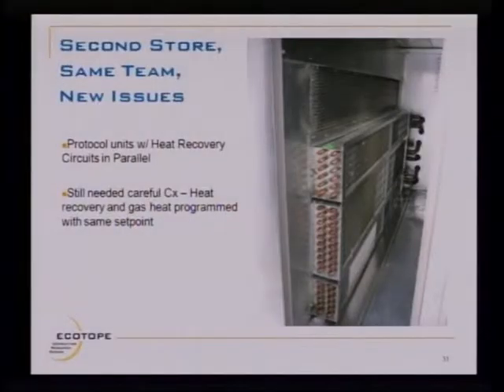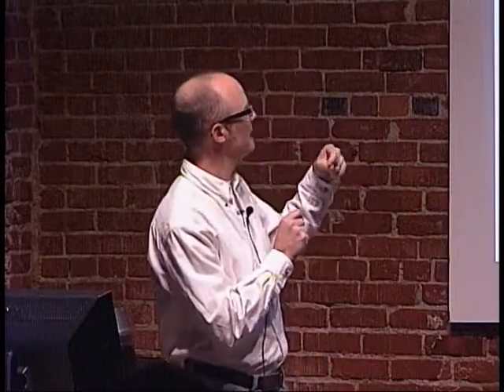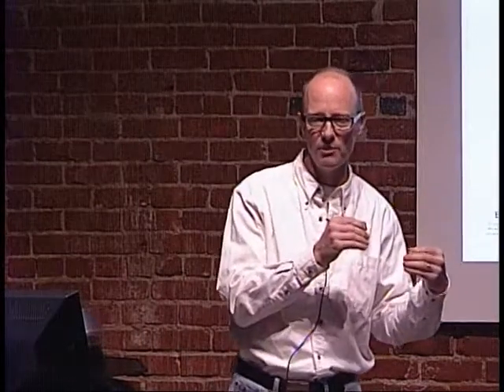The design for this store went to, instead of one big centralized refrigeration rack, they used four smaller refrigeration modules that they call protocol modules, kind of distributed around in the store. And one of those went to refrigeration heat recovery to the hot water, which is a good idea, because there is quite a bit of hot water being used in these stores since they've got delis now.